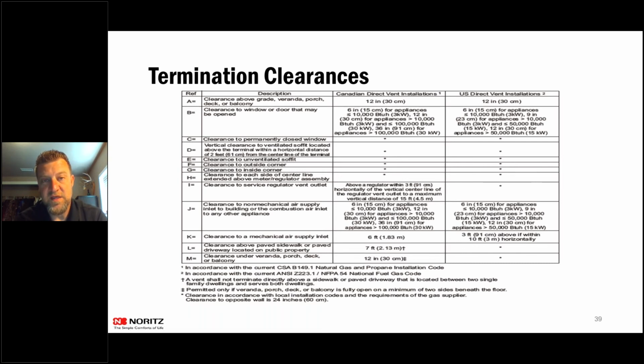So a lot of times the exhaust and the intake are coming out pretty close to where the furnace is. So this would fall within the intake and exhaust of being next to a furnace or a power vent water heater or whatever appliance is bringing its own combustion air into the house. So with that, our exhaust and our supply needs to be at least 12 inches away from our intake and their intake. So that is where that falls into. If you are installing in a retrofit application where they have a large combustion air that's coming into the house, that's when that falls into K.